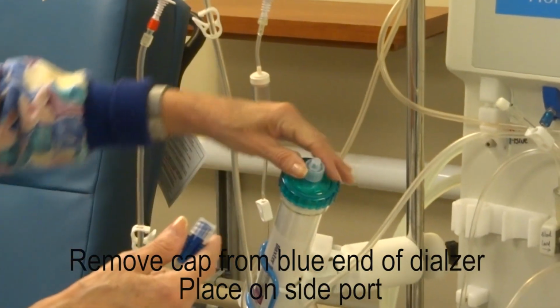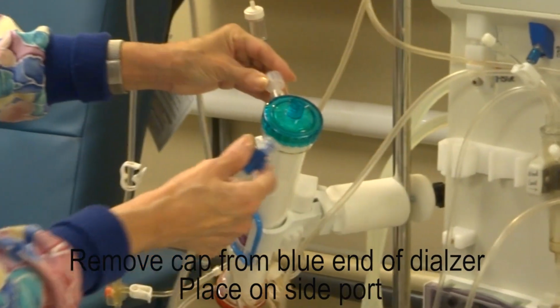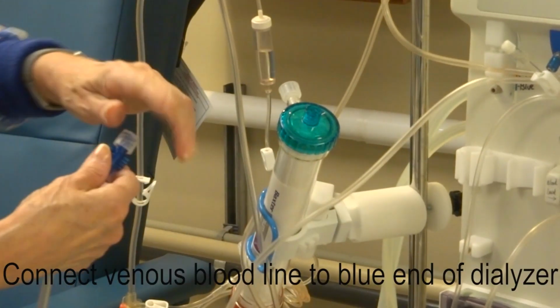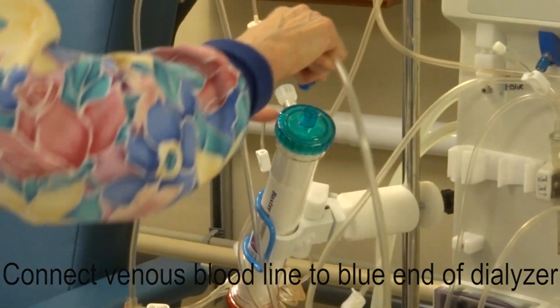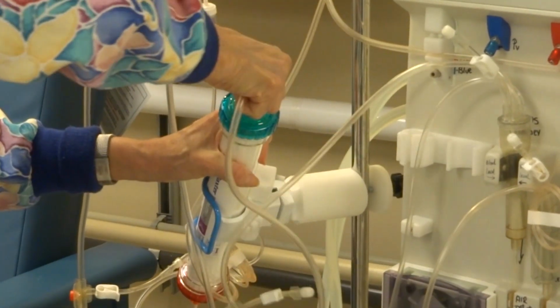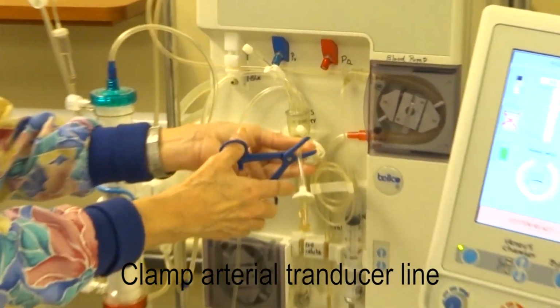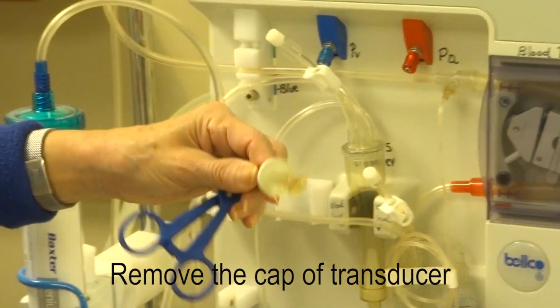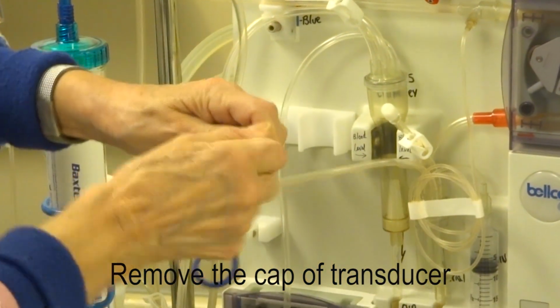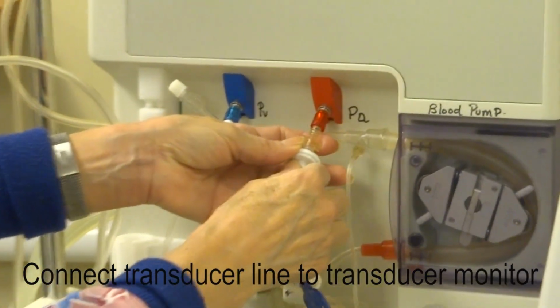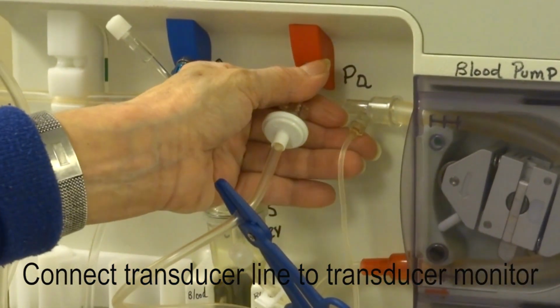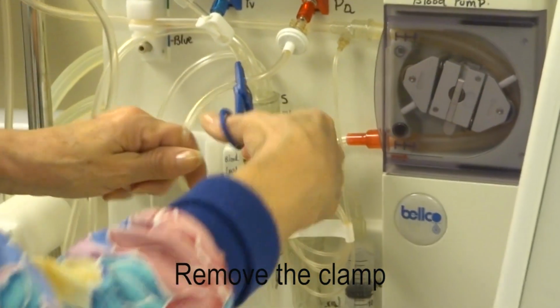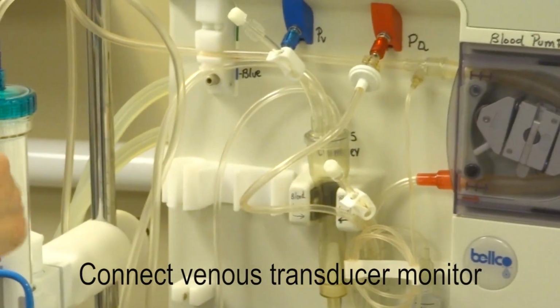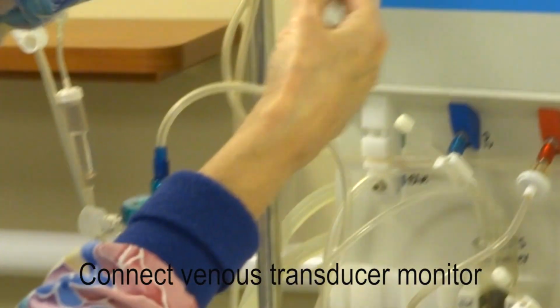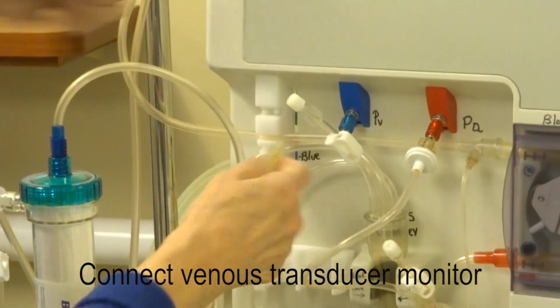Remove the cap from the blue end of the dialyzer to the side port. Connect the venous blood line to the blue end of the dialyzer. We use a blue clamp to clamp the arterial transducer line. Remove the cap of the transducer. Connect the transducer line to the transducer monitor. Remove the blue scissor clamp. Next, we connect the venous transducer line to the venous transducer monitor.